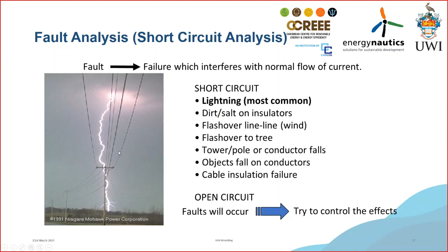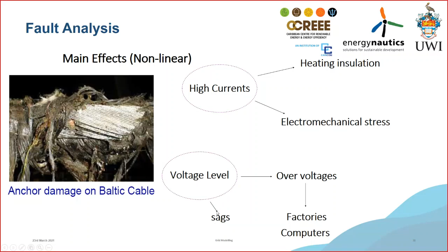You can also have a fault which is called an open circuit fault, which is when at the joint here where I have the conductors meeting at this point here, you can have the loop here, which is a pigtail from here to here, and that burns out, and it becomes an open circuit. So that you see that as a fault also on the system because now I have an unbalanced system. I have a balanced system on this side, on this side, it becomes unbalanced. So that's a fault. The main effect is high currents in terms of heating and electromechanical stress and voltage levels. I can have over voltage, I can have sags, I can have under voltages, all of which can affect my equipment which are on the system.